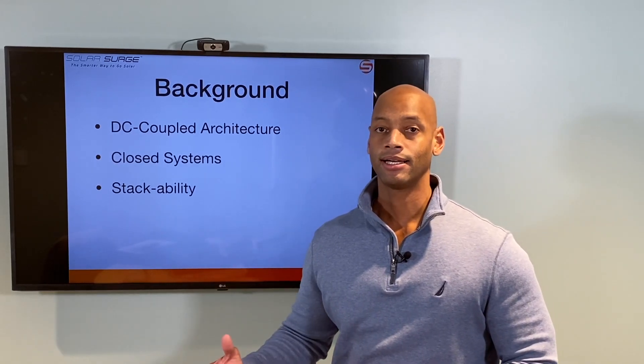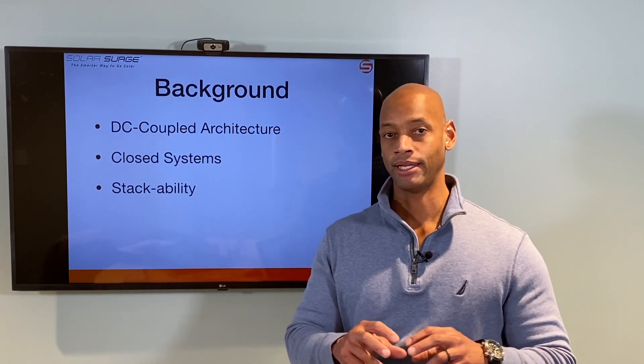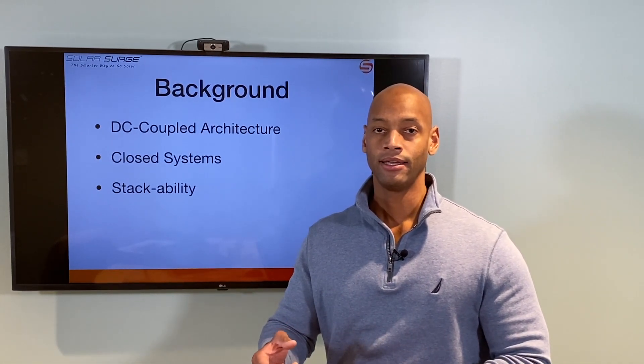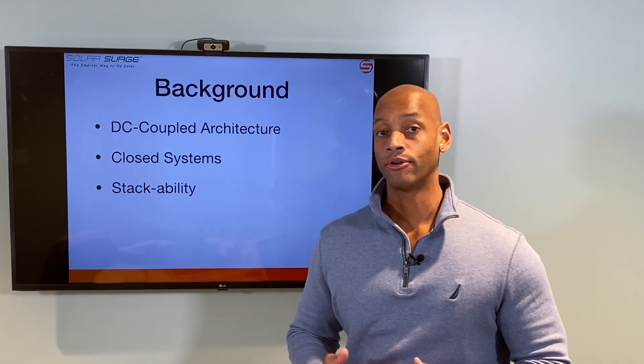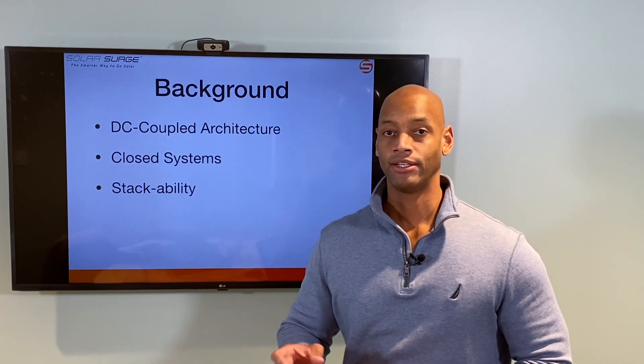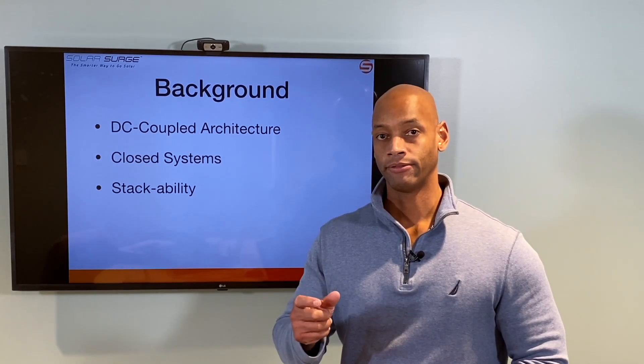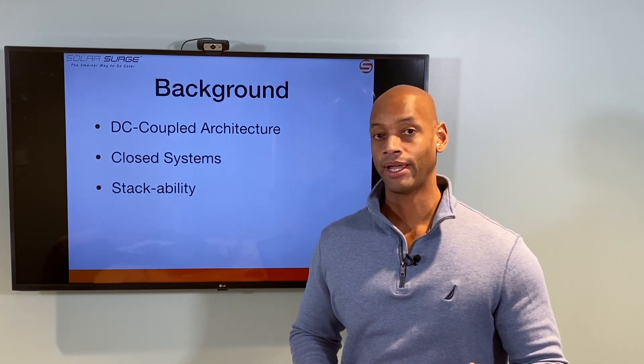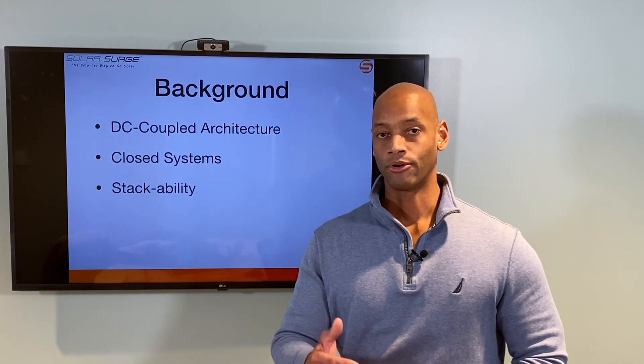There are two main types of battery backup systems: AC coupled and DC coupled. When we talk about coupled, we're really saying where do the solar panels and the batteries meet — on the DC side directly, or after an inversion where it's converted from DC to AC? Both of these are DC coupled systems, which means they will perform better and more efficiently in a grid-down mode, because you can directly recharge the batteries from solar without having to convert it. Anytime you have to convert or transform electricity, there's a little bit of energy lost — most of it as heat.